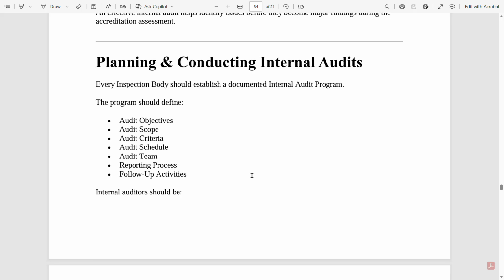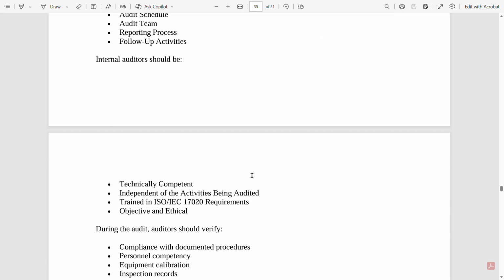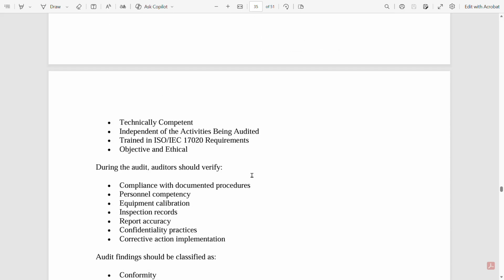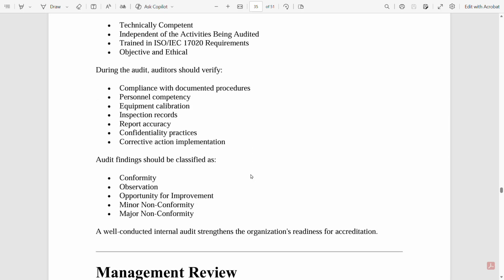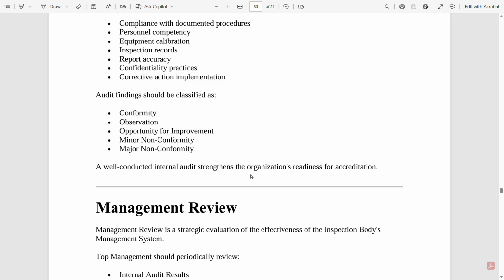Planning and conducting internal audits. Every inspection body should establish a documented internal audit program. The program should define audit objectives, audit scope, audit criteria, audit schedule, audit team, reporting process, and follow-up activities. Internal auditors should be technically competent, independent of the activities being audited, trained in ISO/IEC 17020 requirements, objective and ethical. During the audit, auditors should verify compliance with documented procedures, personnel competency, equipment calibration, inspection records, report accuracy, confidentiality practices, and corrective action implementation. Audit findings should be classified as conformity, observation, opportunity for improvement, minor non-conformity, or major non-conformity. A well-conducted internal audit strengthens the organization's readiness for accreditation.